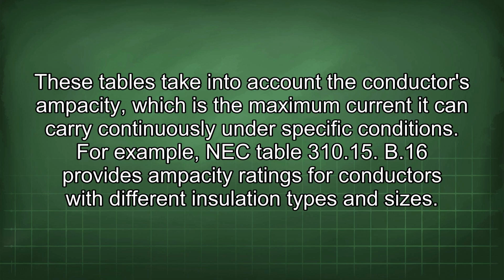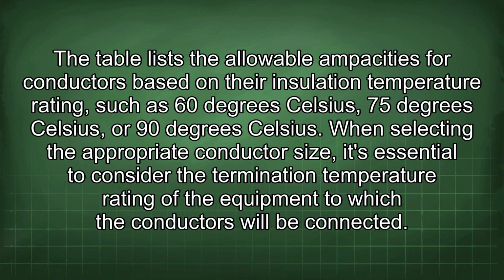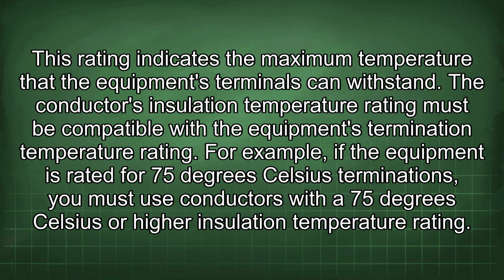For example, NEC Table 310.15(B)(16) provides ampacity ratings for conductors with different insulation types and sizes. The table lists the allowable ampacities for conductors based on their insulation temperature rating, such as 60 degrees Celsius, 75 degrees Celsius, or 90 degrees Celsius. When selecting the appropriate conductor size, it's essential to consider the termination temperature rating of the equipment to which the conductors will be connected. This rating indicates the maximum temperature that the equipment's terminals can withstand. The conductor's insulation temperature rating must be compatible with the equipment's termination temperature rating. For example, if the equipment is rated for 75 degrees Celsius terminations, you must use conductors with a 75 degrees Celsius or higher insulation temperature rating.